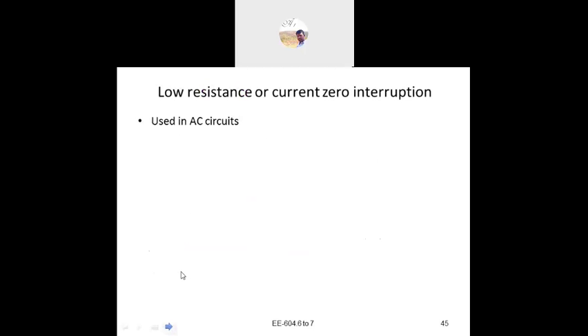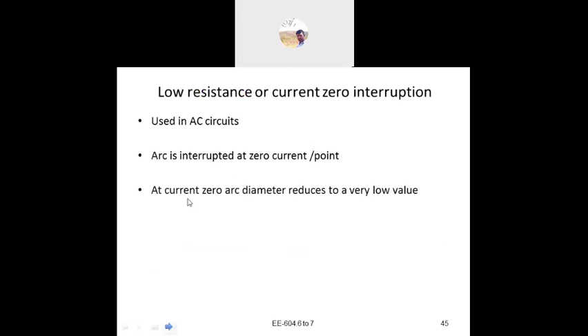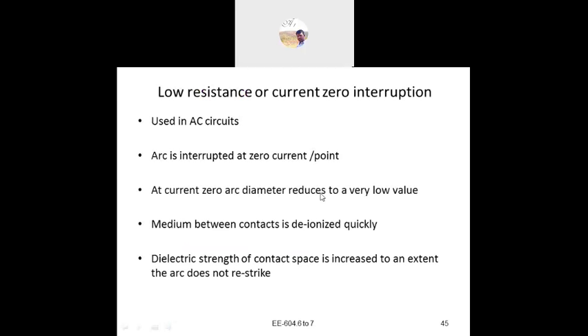Next is the low resistance type of arc quenching. This method is used in AC circuits, interrupting at zero current. At current zero, the arc diameter is reduced to a very low value. So the medium between the two contacts is deionized completely, and the dielectric strength of the contact space increases. So the arc does not restrike in this type.